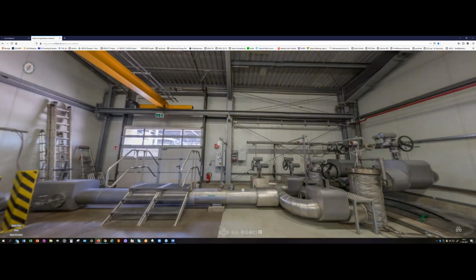Within our brine facility hall, this is the hot brine coming out of the production valve. We have two filter units where we filter fines out of the hot brine, which we especially need after restarting the whole system after a maintenance shutdown for a longer period. Restarting the brine pump mobilizes fines out of the reservoir, and they are filtered out here above ground.